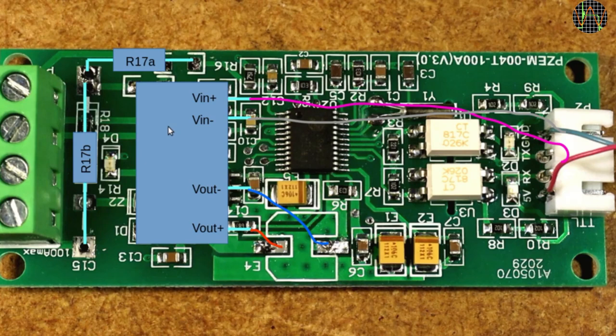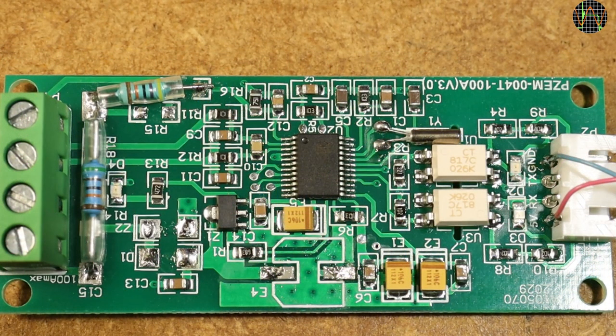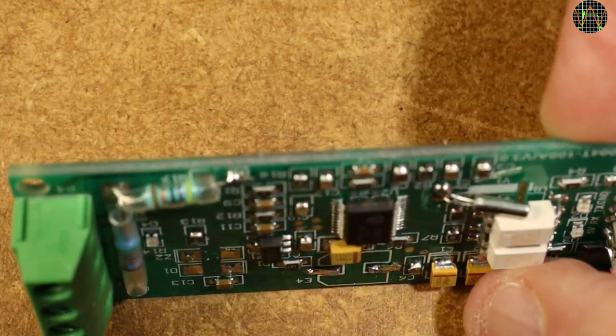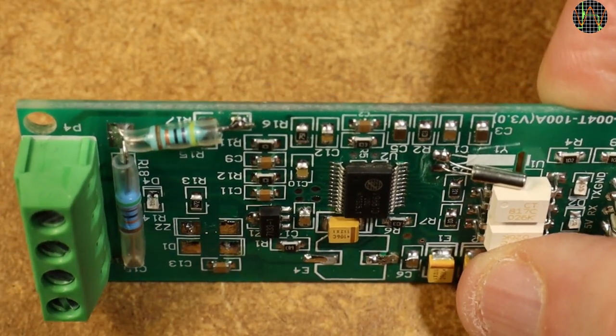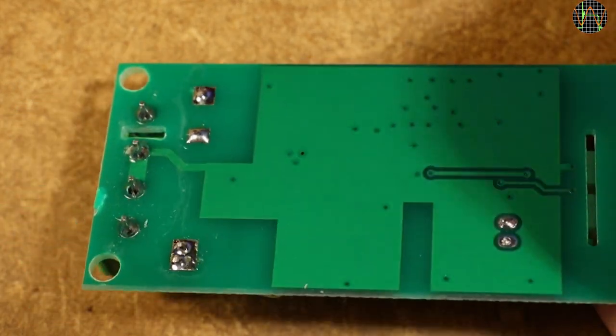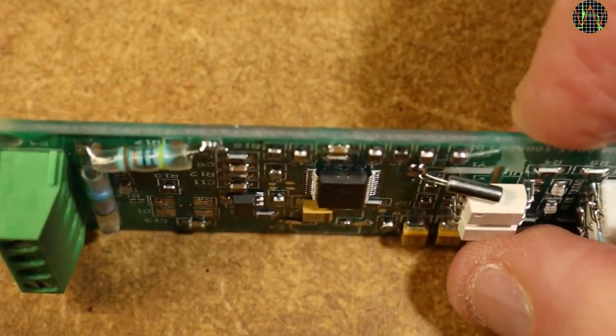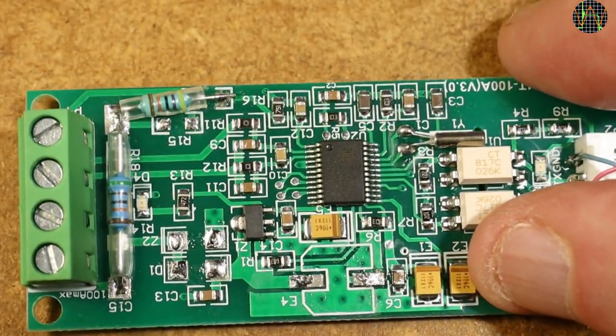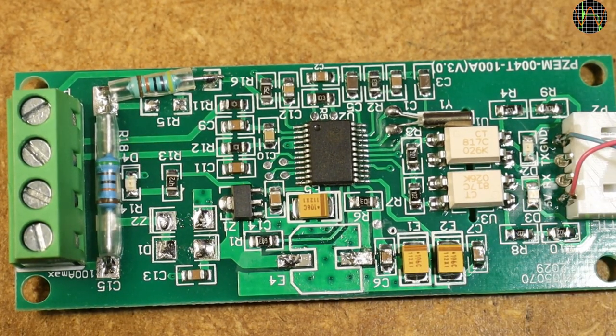The 12 volt output of the DC to DC converter conveniently attaches to the pads where the electrolytic capacitor used to be. The thin wires already attached to the USB connector will fold over the other way and run double isolated to the input of the converter. The two new resistors R17A and R17B to replace R17, the 1 megohm that isn't 1 megohm, are installed. Because R17B has the 0.05 ohm resistor for the current shunt underneath, I decided to put them in some transparent heat shrink sleeving for extra protection.